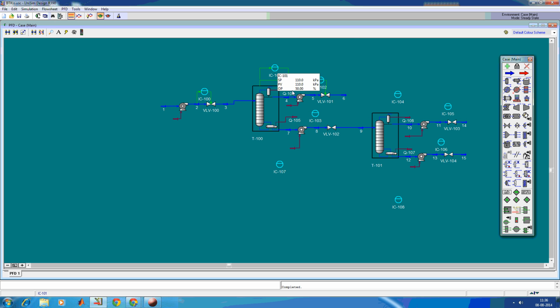Now over here you see the way the dynamic simulation would run, the controller would say give me 5% increase in cooling duty. HYSYS will immediately give 5% increase in cooling duty. In practice though, what will happen is the controller says give me more cooling duty, cooling water will increase, tubes will become colder, and then you will start getting more condensation. You see what I'm saying? So there is a dynamic lag between what the controller asks and what the duty should be, and that lag is not there in HYSYS.